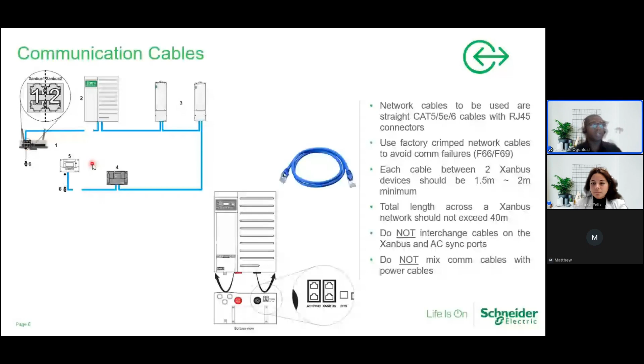If you're using the Insight facility in the system, like what we have here, you have to put a terminator at the channel you're using. Starting with the previous setup we had, every Xanbus device has two Xanbus ports. At one port where you're starting the sequence, you put a terminator, goes through a daisy chain to the other accessories and equipment, then to the final device, which in this case is the Insight facility. At the open port of the Insight facility, on the channel you're using, you put a terminator to signify where you're starting and stopping the network. Again, this is only for communication terminators, not for the AC sync.